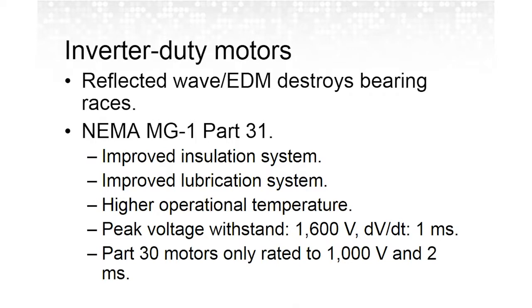So what NEMA has done to address that is create a standard for what is called an inverter duty motor. The standard is NEMA MG1 Part 31, which should not be confused with Part 30, which some vendors also state are inverter duty motors, but there are very important differences between the two. With NEMA MG1 Part 31 motors, we have an improved insulation system on the windings. We have a better lubrication system for the bearings to withstand higher operational temperatures.